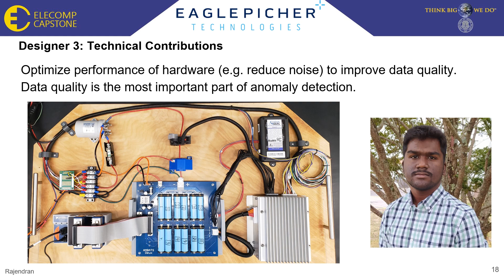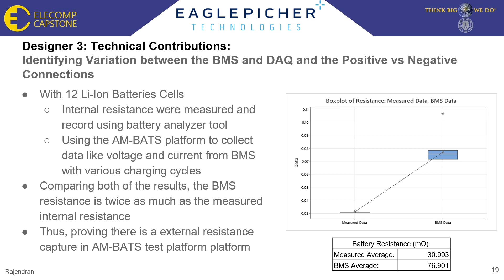One of the first tests I did was to see if the resistance values are accurate. To do so, I used 12 lithium-ion batteries to measure internal resistance using a battery analyzer tool, and with the same batteries, voltage and current were collected from the BMS to calculate the change in resistance while charging. The results show that the BMS calculated resistance is an average of 77 milliohms, while the measured resistance is at 31 milliohms, proving that there is an external resistance captured by the embedded platform.